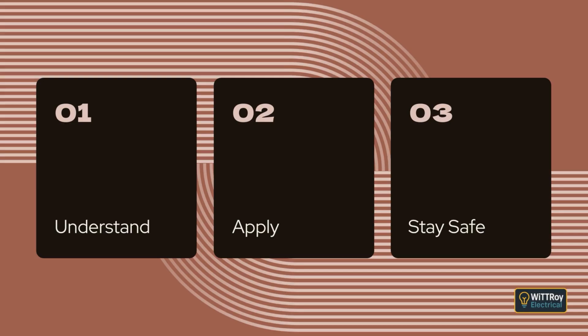Where installed in a location that is not readily accessible for the connection of a fixed or stationary appliance or a luminaire, the socket outlet shall be securely fixed to a structure or support to ensure that no mechanical strain is placed on the installation wiring connections when inserting or removing a plug to the socket outlet. The socket outlet need not be fixed in position where the installation meets the following conditions. Cable connections are not subject to undue mechanical stress. The wiring system where likely to be disturbed is supported. The wiring system where installed in a suspended ceiling is supported. Conductors are flexible or stranded type, and insulated unsheathed cables, including exposed cores where sheathing is removed, are enclosed.